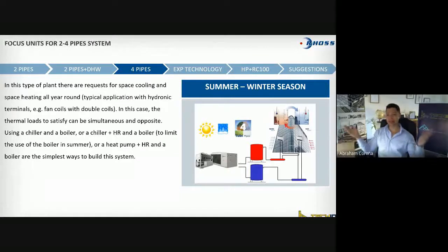Is exactly that. Depending on, it could be that picture you have there, you are in the mid-season, you have one face of the building at the sunlight, so you're getting heat there, you may need air conditioning. The other side is in the shadow, you may need heating in different offices. So it could be a system where you can have an independent or simultaneous demand of heating and cooling. At this stage, we're talking about only the system. We are not talking about the EXP system, polyvalent technology, or RHOSS.